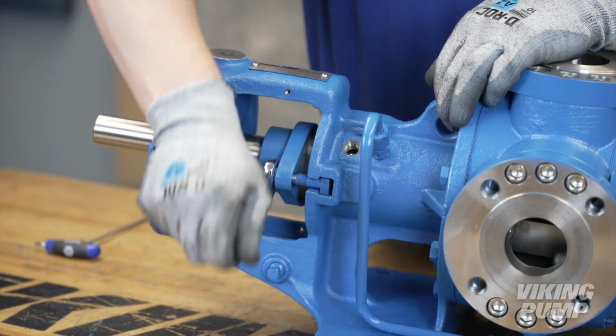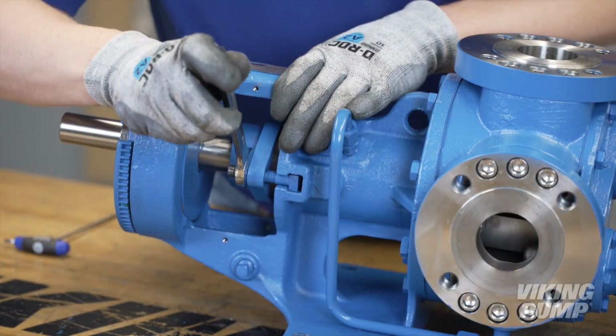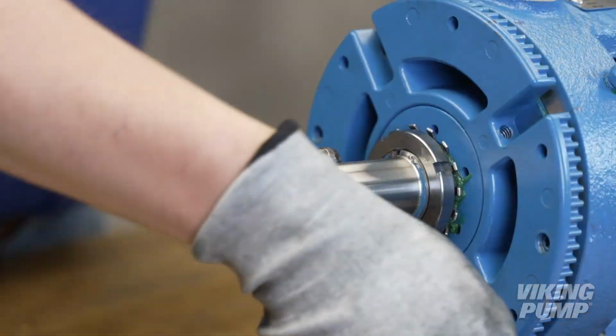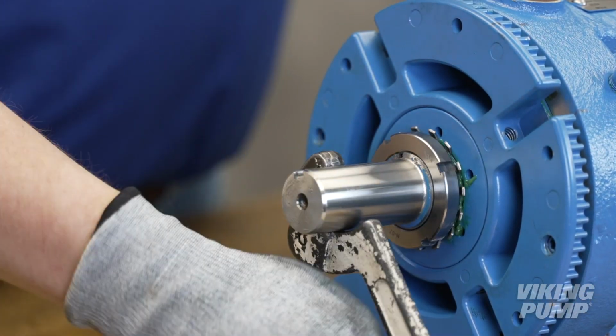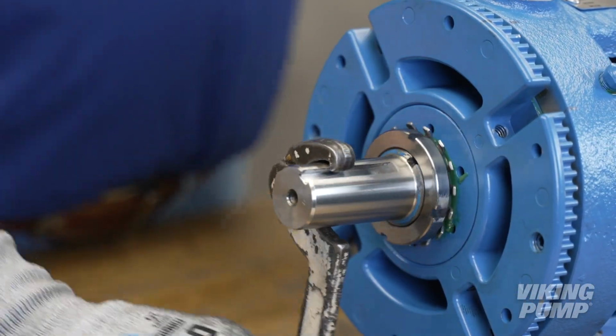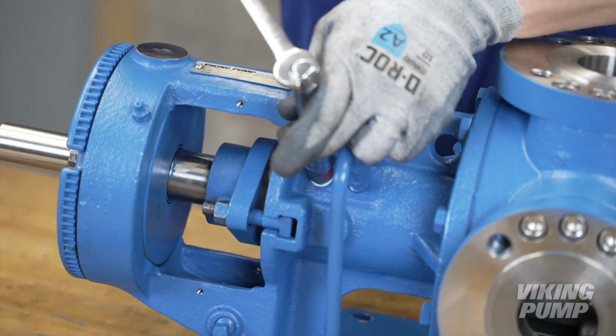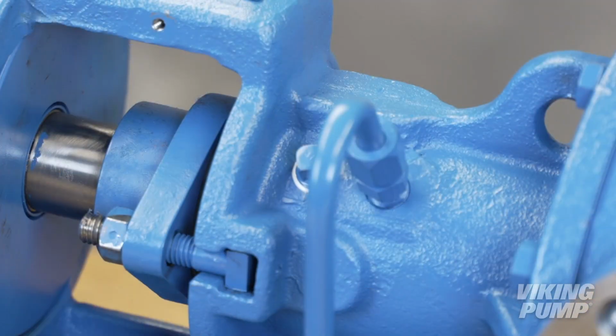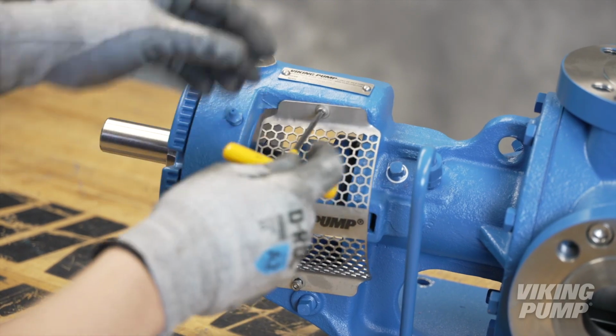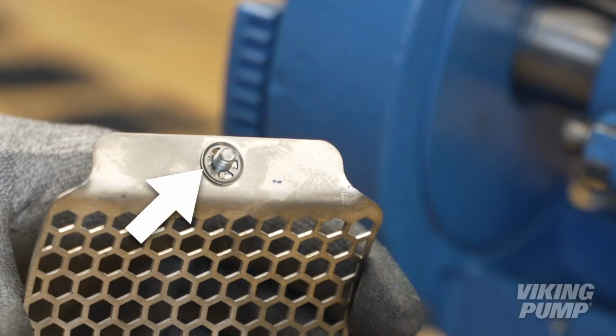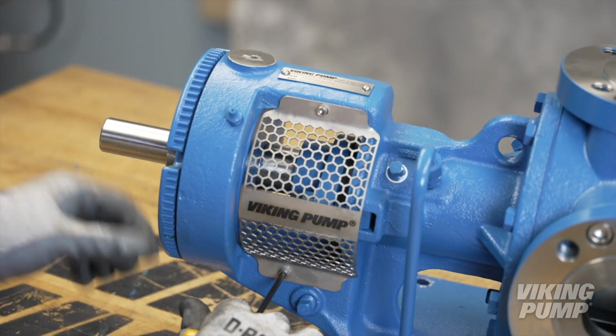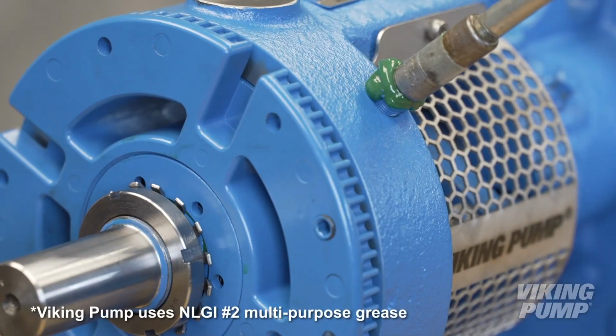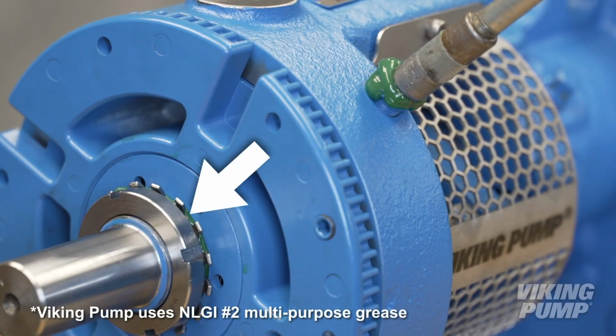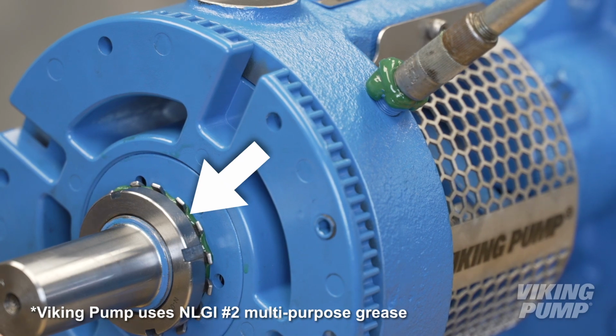Next, fully tighten the seal holder lock nuts. Turn the shaft to ensure the pump turns freely. Using appropriate thread sealant, install plugs into the seal access holes. Reinstall the window guards. Ensure that the retaining washer is placed between the guard and bracket faces. Finally, grease the bearing housing until grease begins to appear around the lock washer.